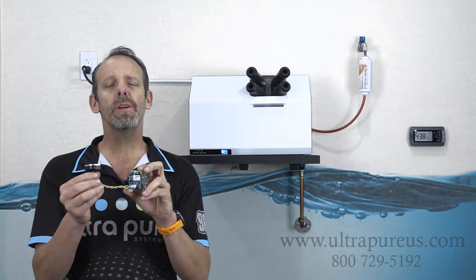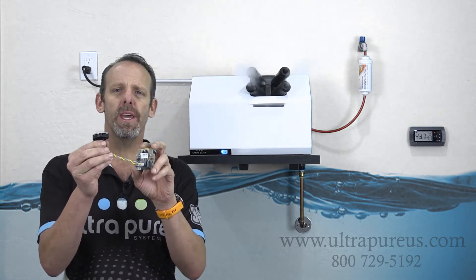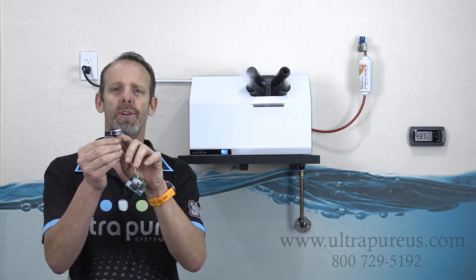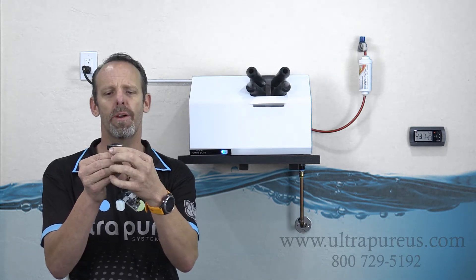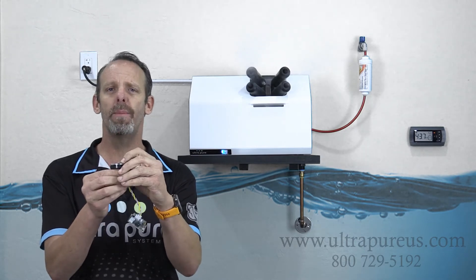When that circuit calls for humidification, it applies that voltage into a very high frequency with this transducer that is actually on the water bed. The whole device isn't in the water — just the small plate on top is actually touching the water bed.